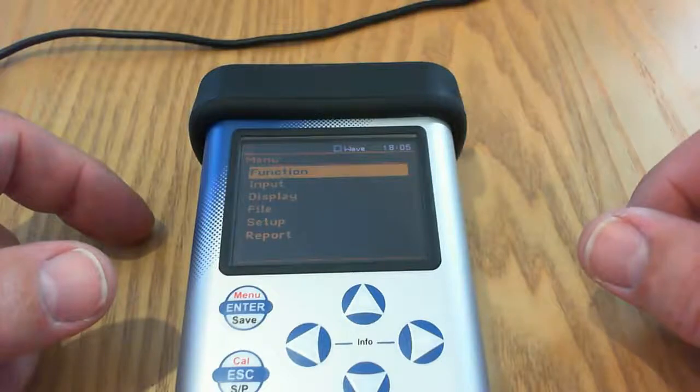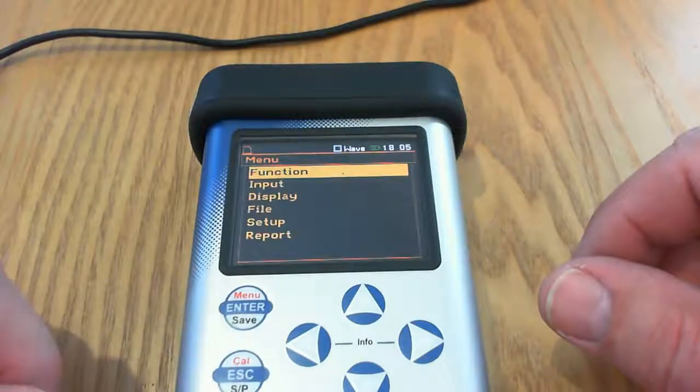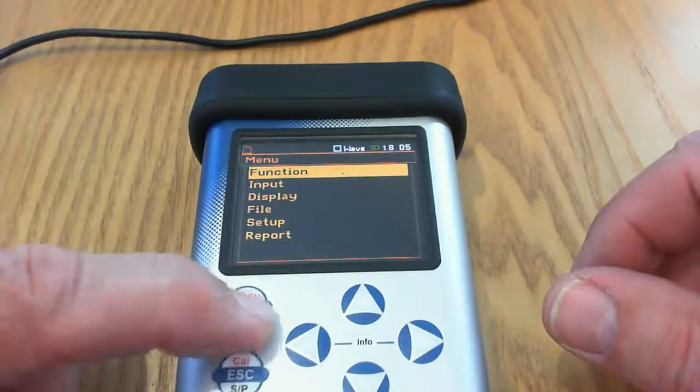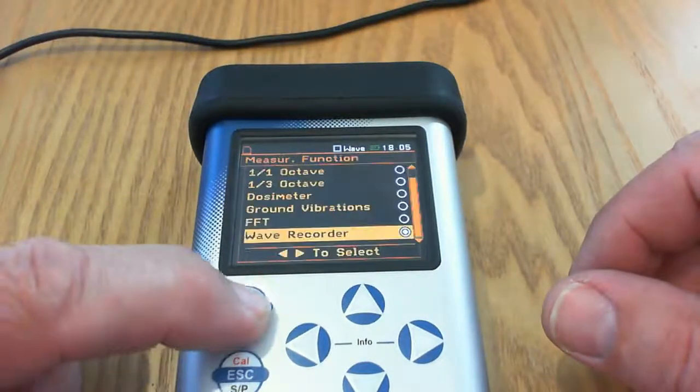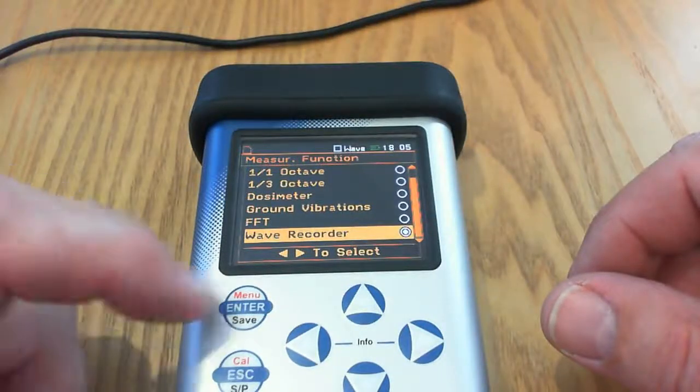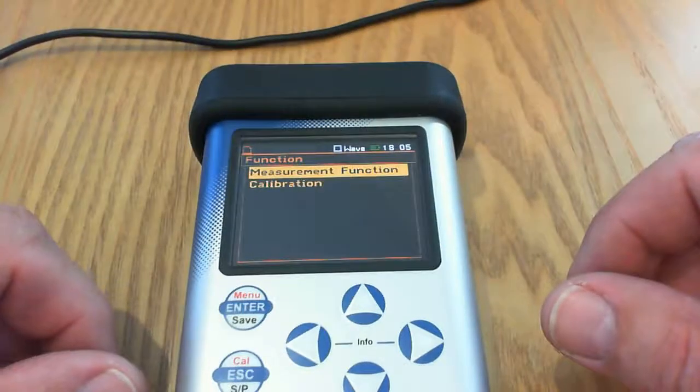First thing we need to do is get the analyzer into wave recorder mode, so we go into the function menu and choose the wave recorder option, assuming it's installed and ready to go. Press enter to accept that.